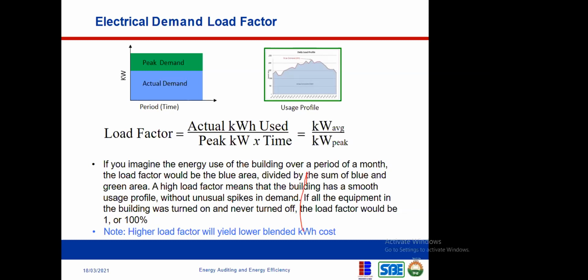So, like I earlier said, to put this into perspective, imagine you have a certain capacity of generator, say 20 kVA, and you're only making use of 10 kVA of it - which means 50% of that generator is lying fallow, not being used - which means you could connect to your neighbors and begin to improve your load, your demand load factor. So in actual sense, that's what load factor is: the actual power or energy that you're taking divided by the possible amount of energy you could have gotten out of it. I don't know if that's clear enough.